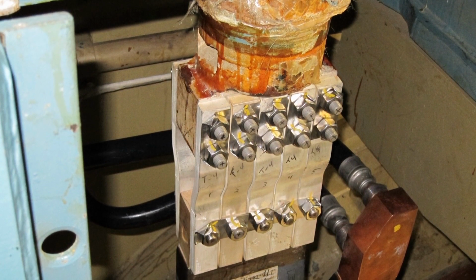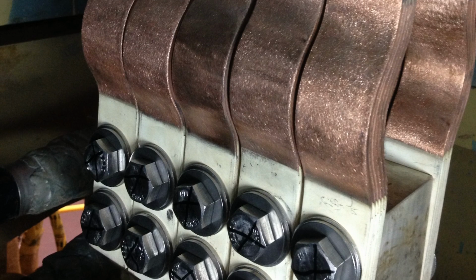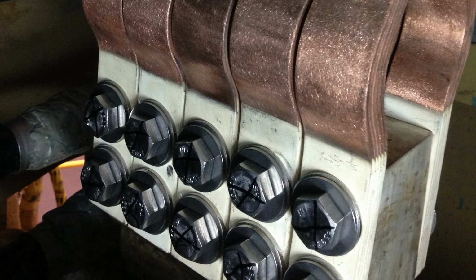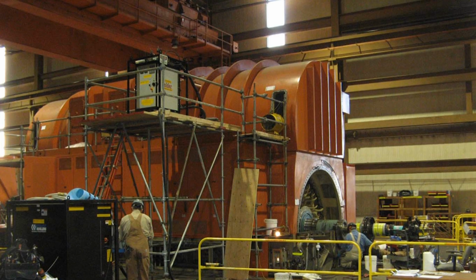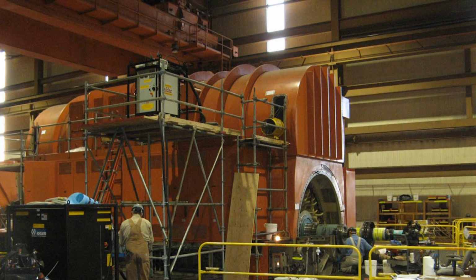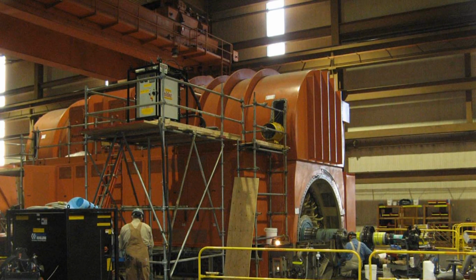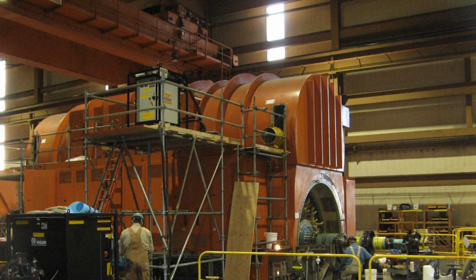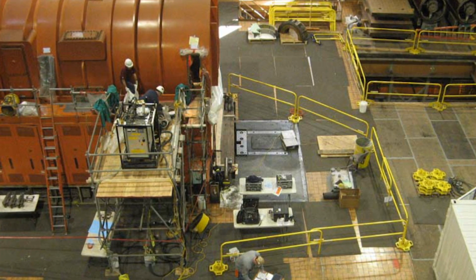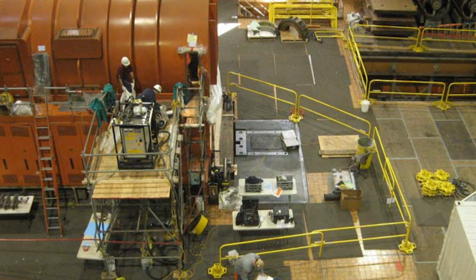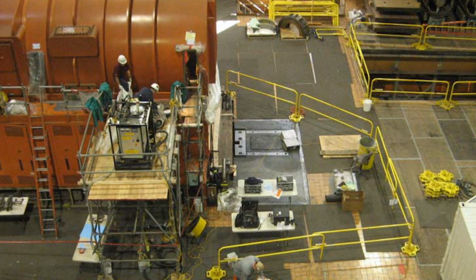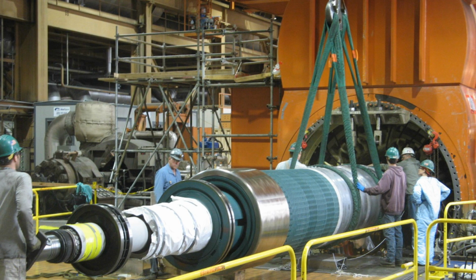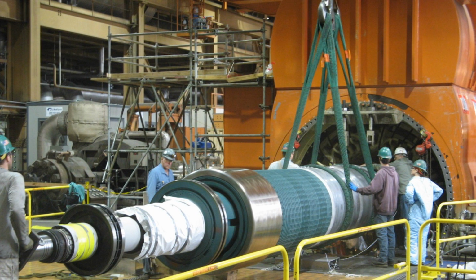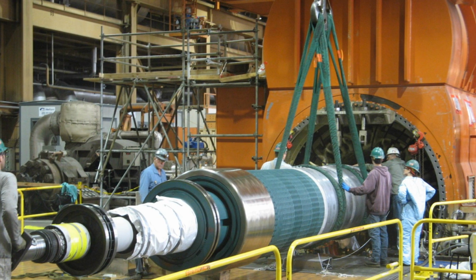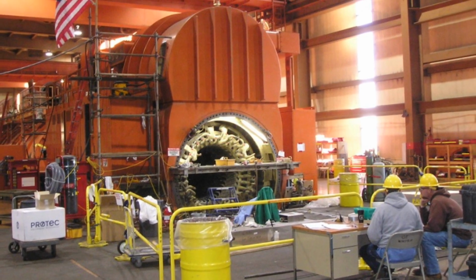The bottom row of holes for the extension cap were aligned with the existing tang bolt holes, and the cap was brazed to the tang using an induction heated brazing process. The extension cap added length to the tang to allow the addition of the second set of bolt holes. To accommodate the extension of the connection ring tang, the generator bus connections were shortened. These modifications were done by GE. They did not require disassembly or removal from the stator. Concurrent with this modification, inspections and extensive resonance testing was conducted and analyzed on the generator stator. Specialized VibroSystM fiber optic vibration and temperature probes were installed on the stator connection rings.